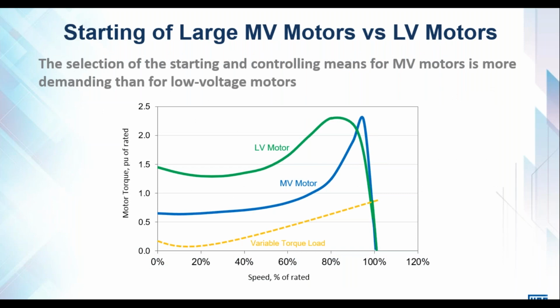Right, so I'm showing why it is so important on medium voltage motors to do a specific analysis of a start condition. Why you need to take more design consideration or analysis into consideration, and that is because low voltage machines we supply off the shelf. They are generally designed with very high starting torques and very high breakdown torques, because they need to cover a multitude of applications without specific analysis for each and every application.